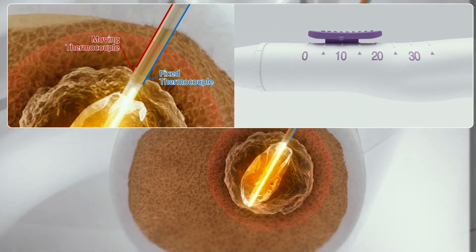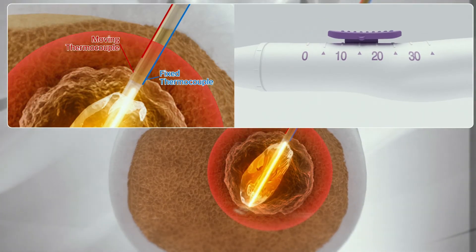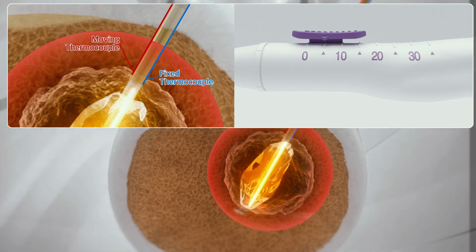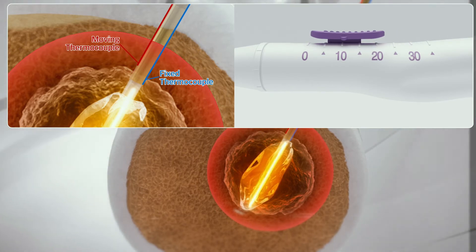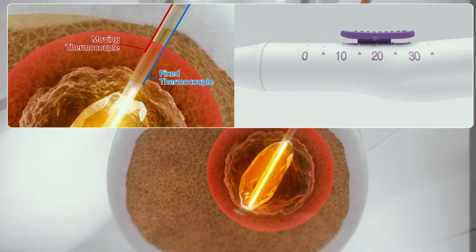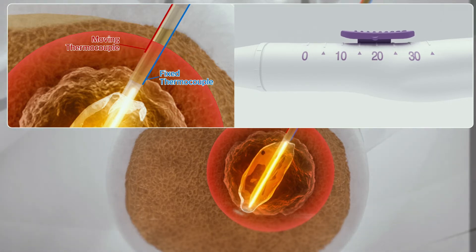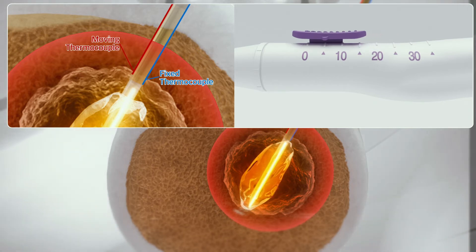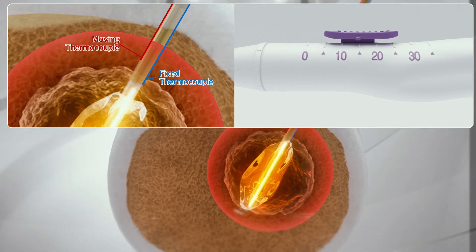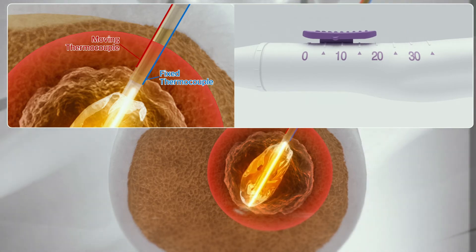The main advantage of the BMDT electrode is that it has two thermocouples: one fixed and the other movable. The fixed thermocouple measures the lesion temperature, while the moving thermocouple allows monitoring of thermal spread of the ablation in real time, including pedicle temperature and surrounding structures such as the nerve root and spinal cord. With these two thermocouples, you can perform ablation on bone metastases more safely.